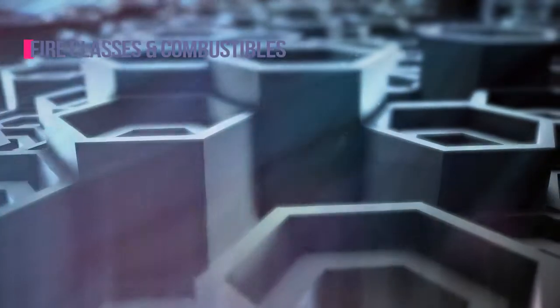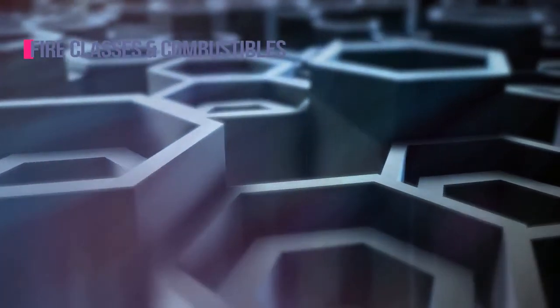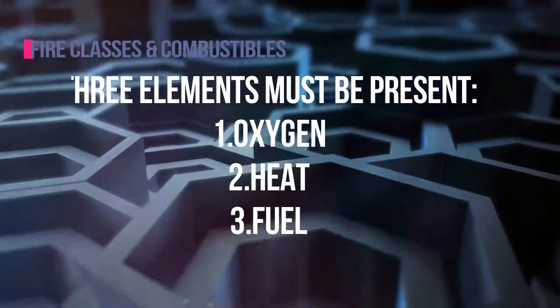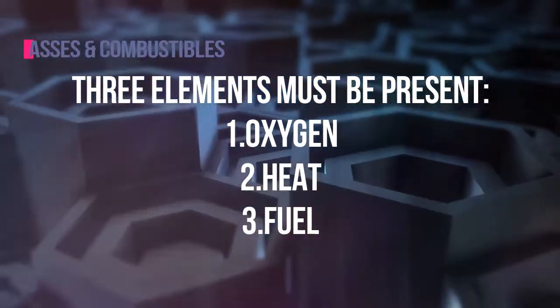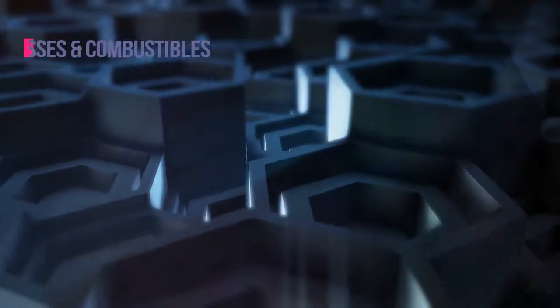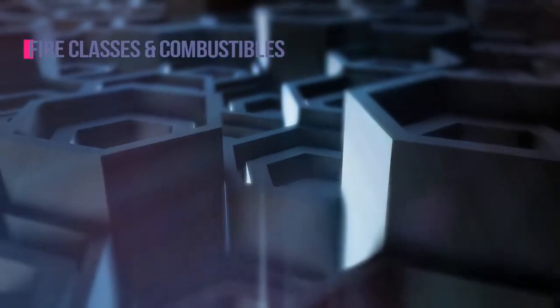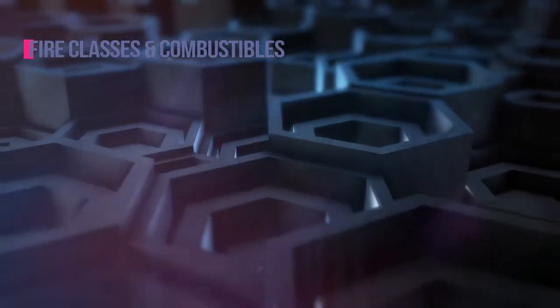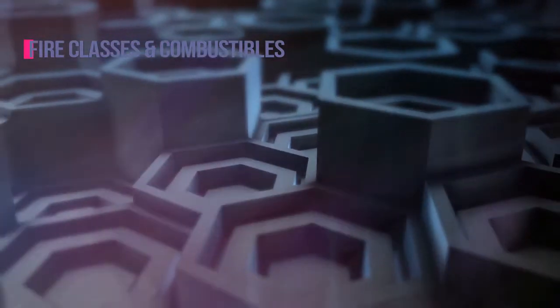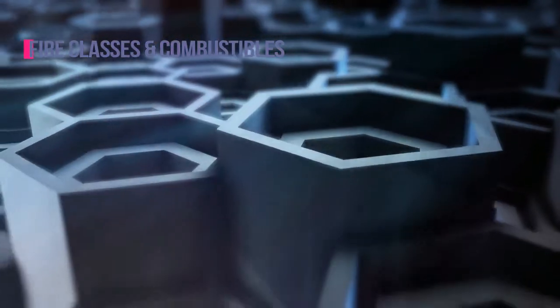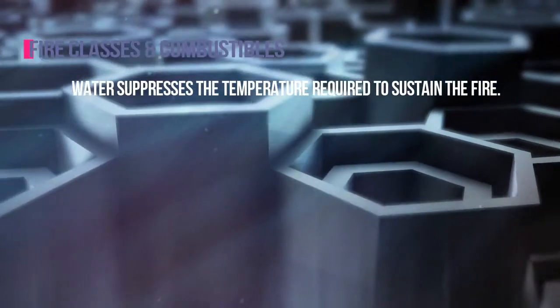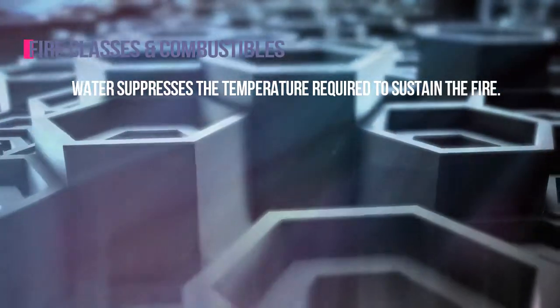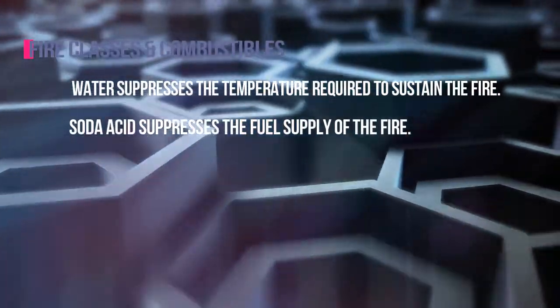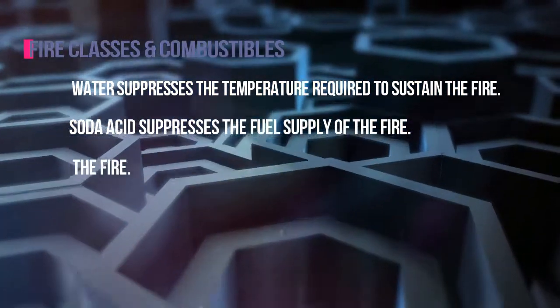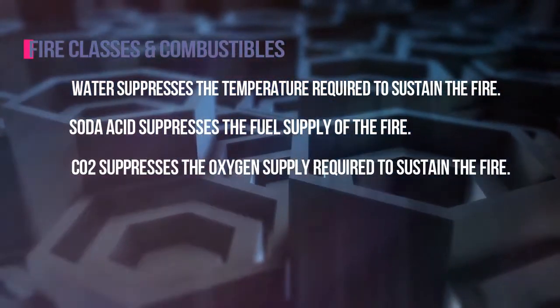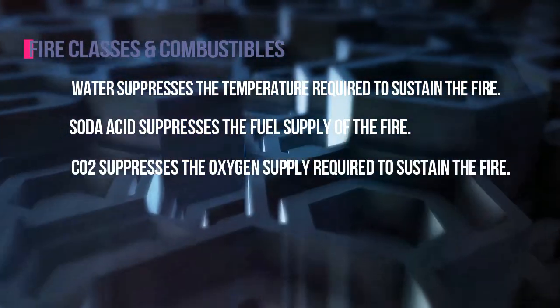For rapid oxidation to occur, or as we know it, a fire, three elements must be present: oxygen, heat, and fuel. Each suppression medium affects a different element and is therefore better suited for different types of fires. For example, water suppresses the temperature required to sustain the fire. Soda acid suppresses the fuel supply of the fire. CO2, or carbon dioxide, suppresses the oxygen supply required to sustain the fire.